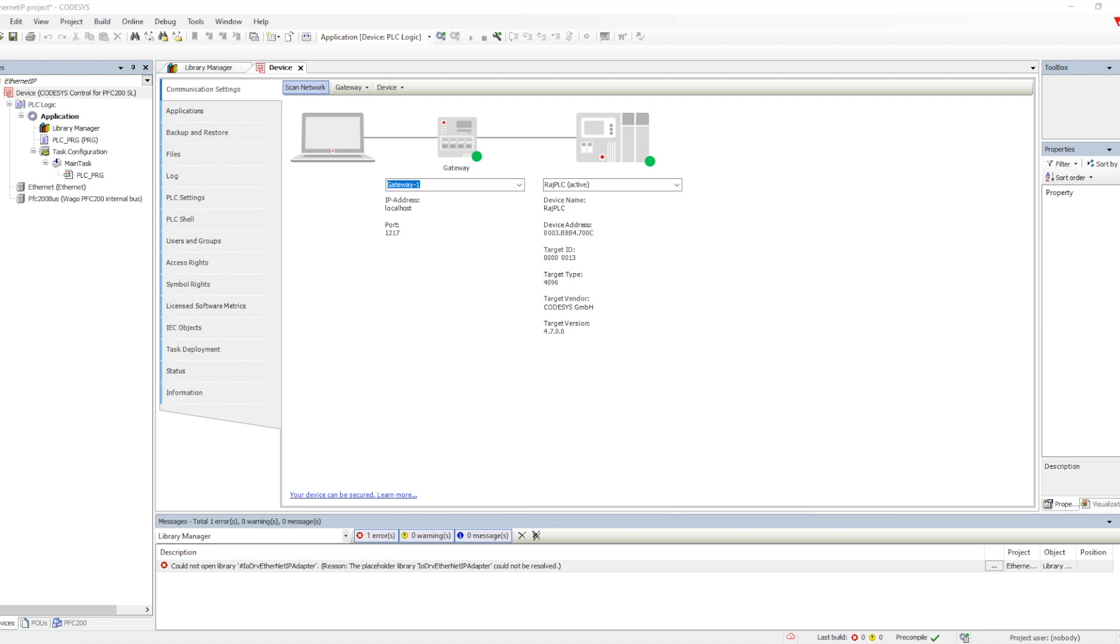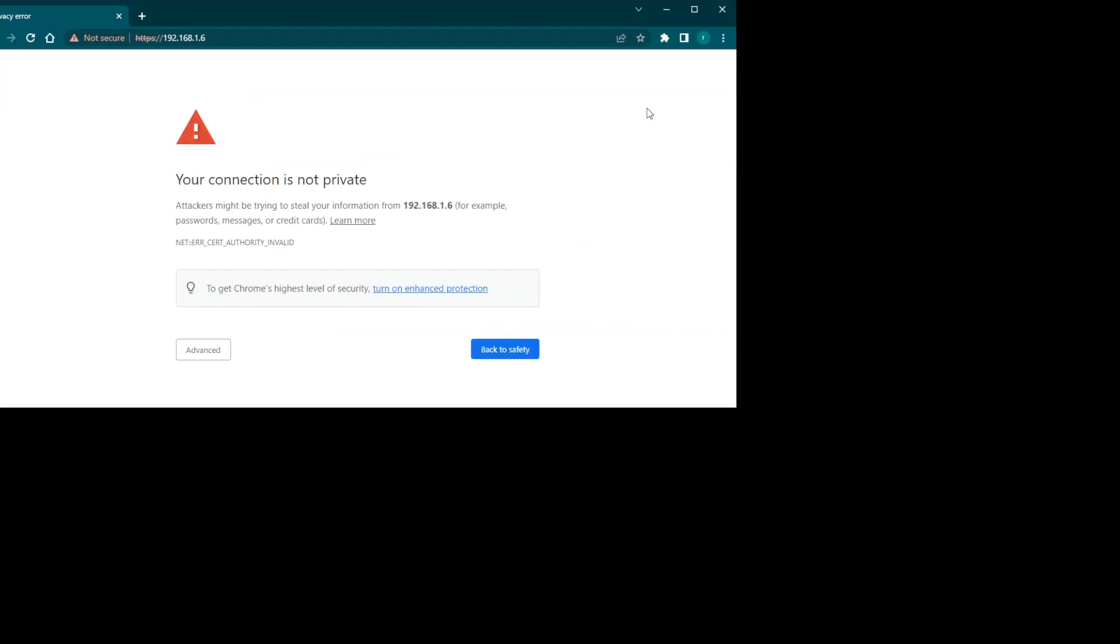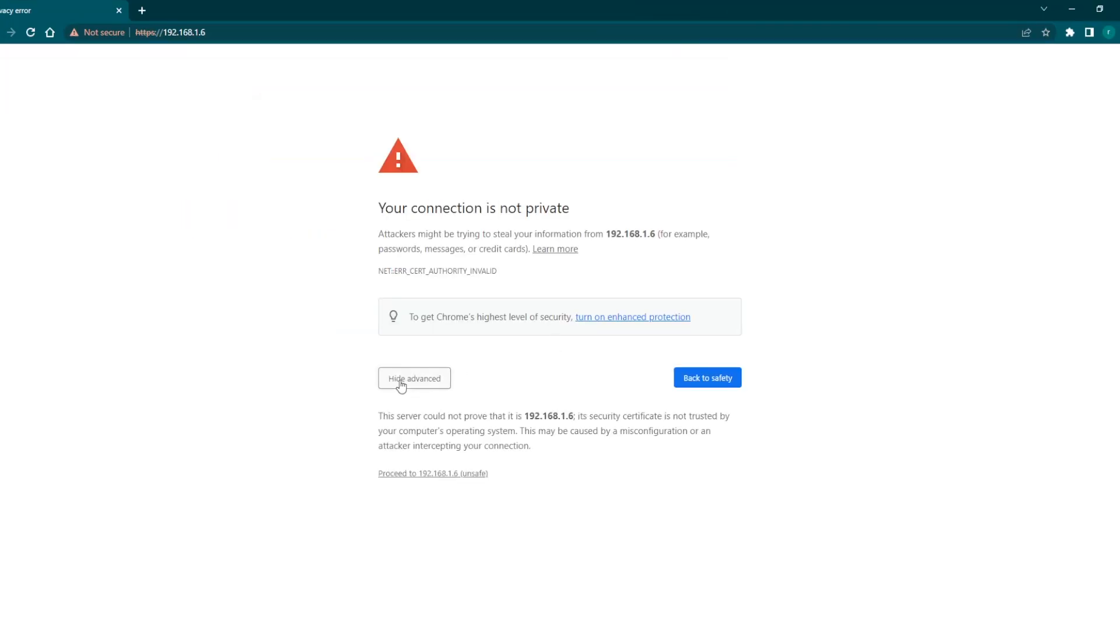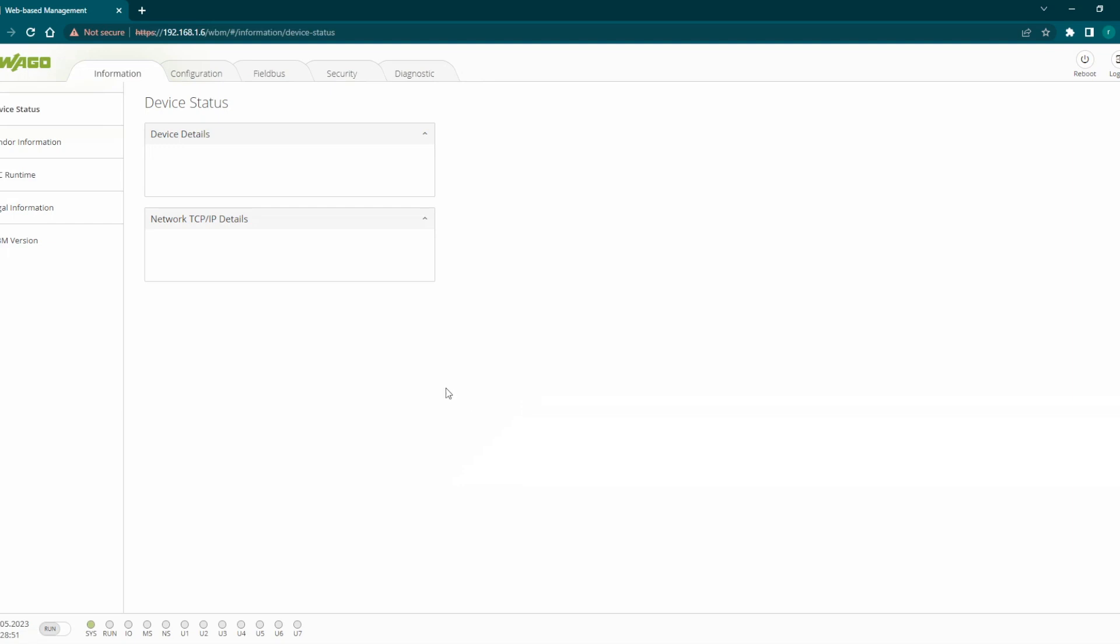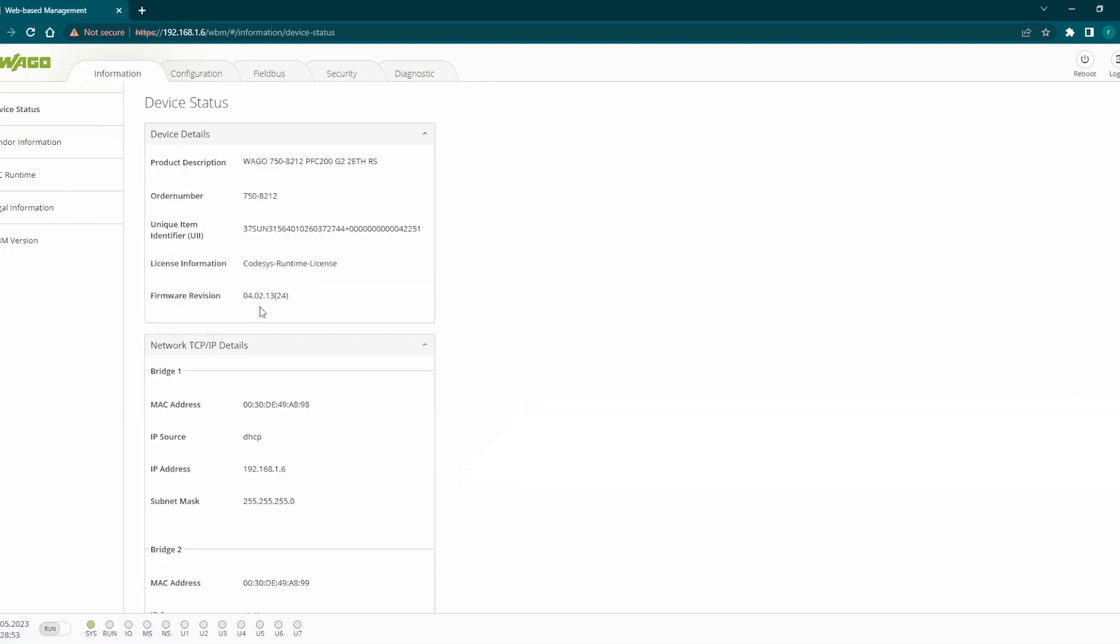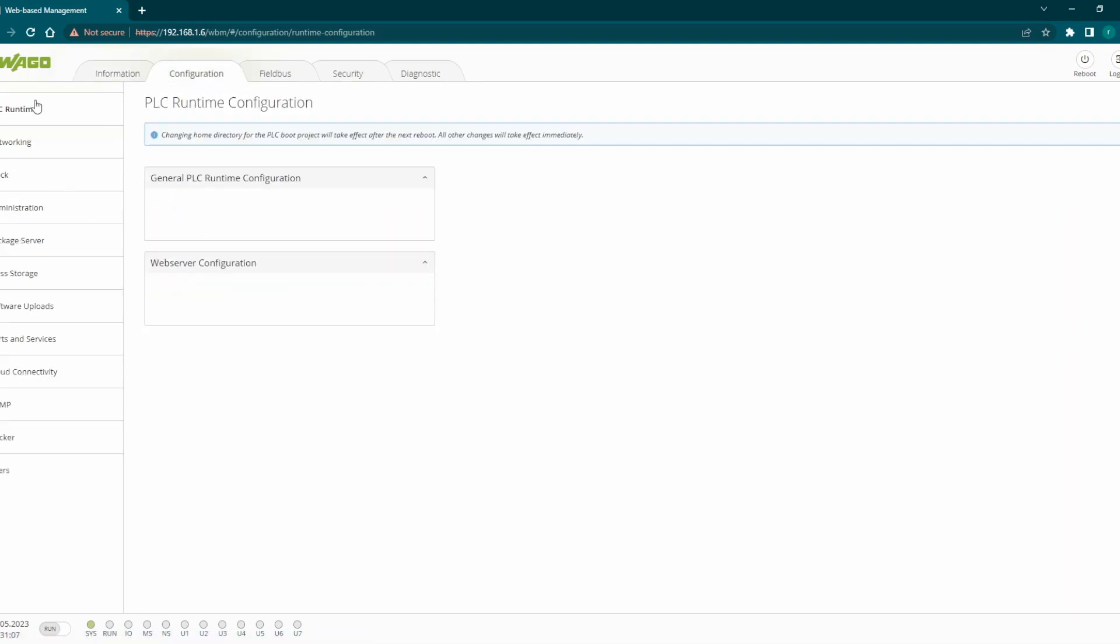What we need to do is go to the web server management of the WAGO PLC. It is default one when we upgrade the firmware, it is admin and WAGO, the username and password. If you see the firmware has been upgraded.